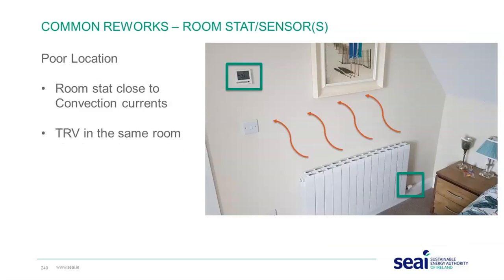Another one as well is room stats. This is something that comes up a fair bit. There's two things in this image. One, the room stat on the wall is too close to the radiator. That room stat's going to get a false sense of temperature. So ideally, consider where the room stat is going to be installed so that it gives a good accurate guide to the room temperature. Secondly, there's a TRV on that radiator.